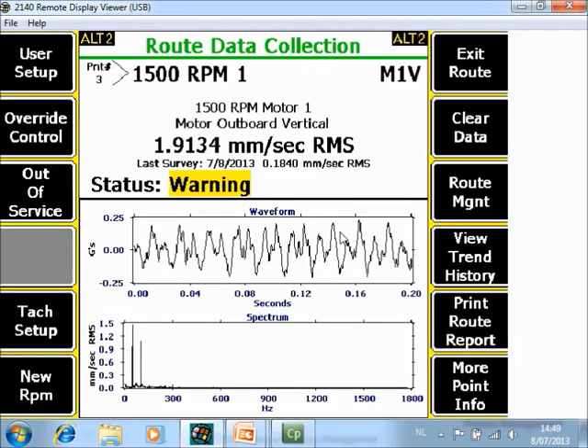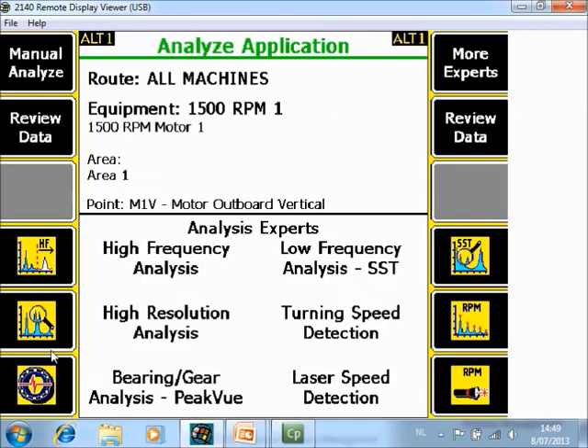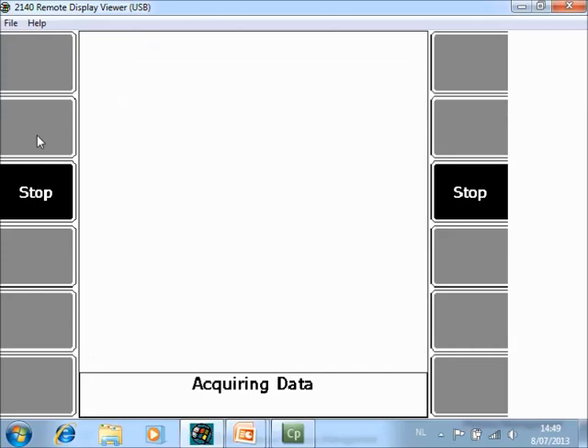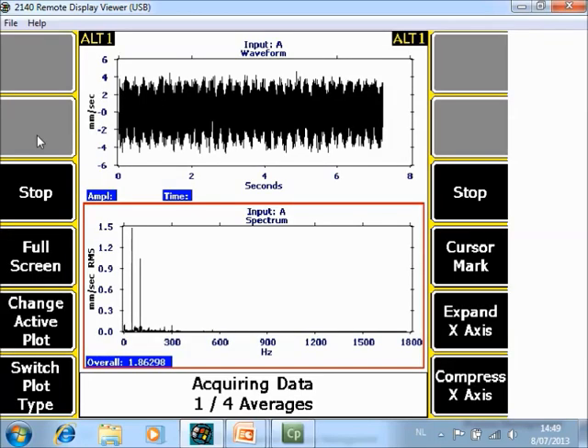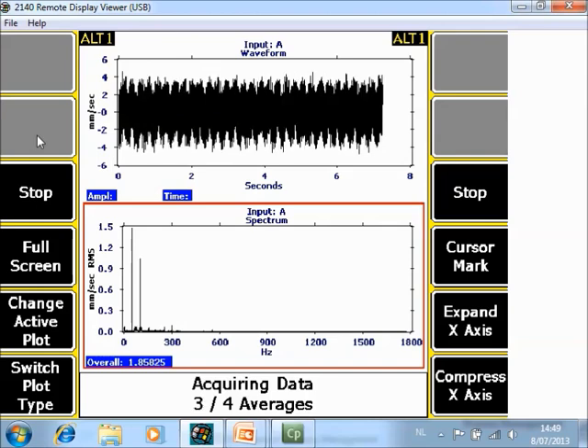If you want to collect additional data with more resolution, go back to ALT 1 and run Analyze F12. Select F5 for high resolution analysis and push F3 to start data collection. It will collect data with the same Fmax but with 4 times higher resolution, so data collection will also take 4 times more physical time.